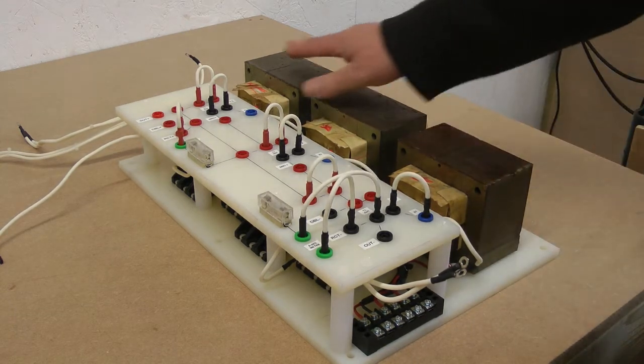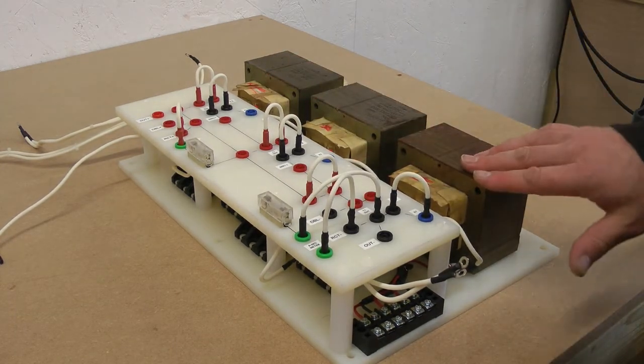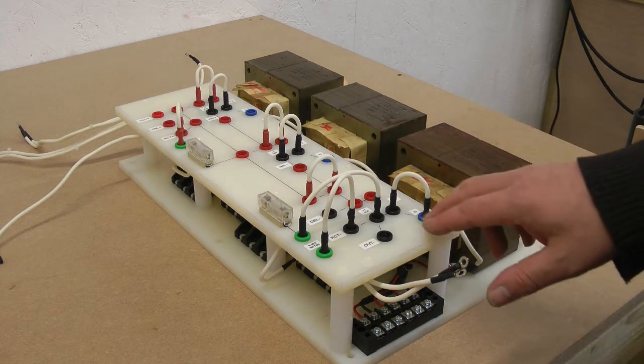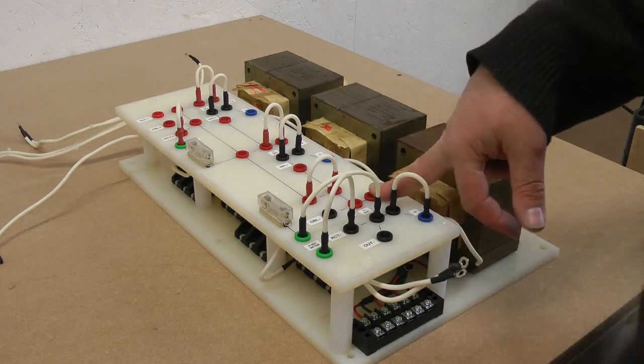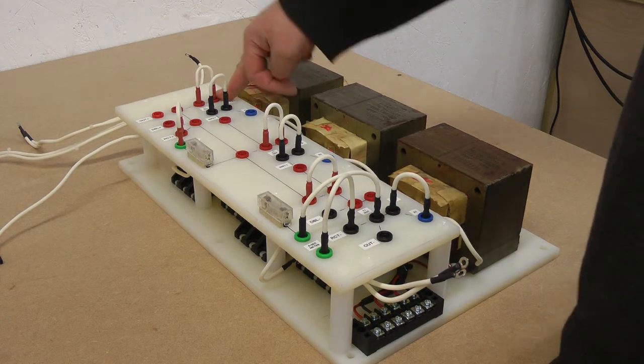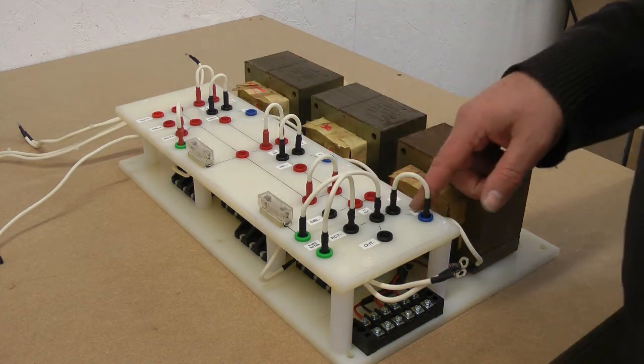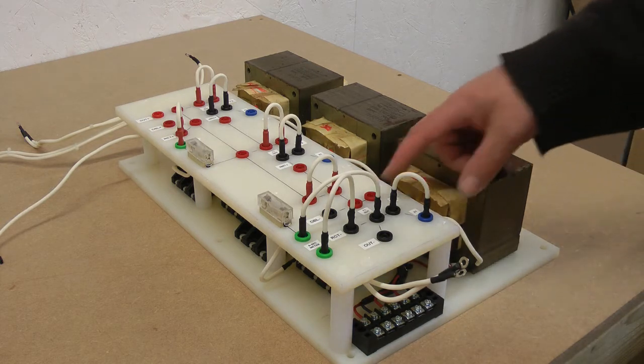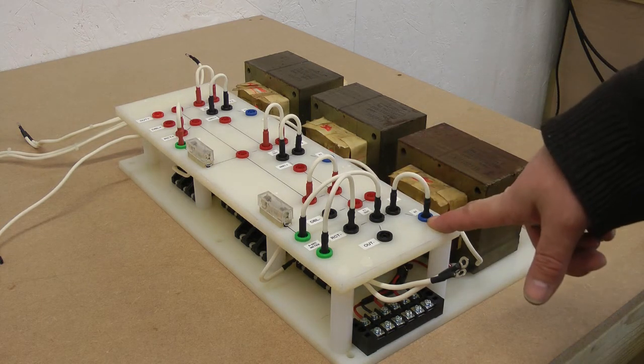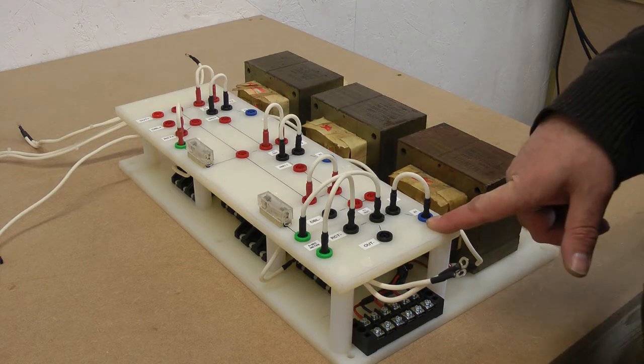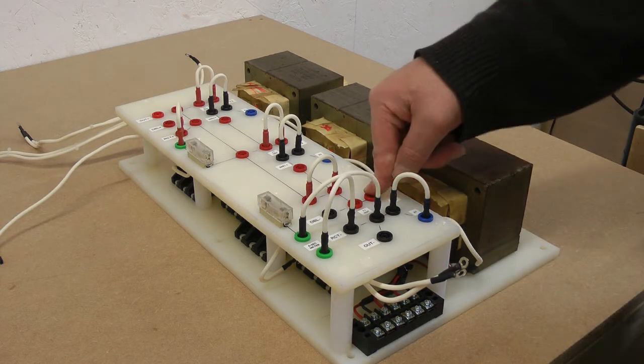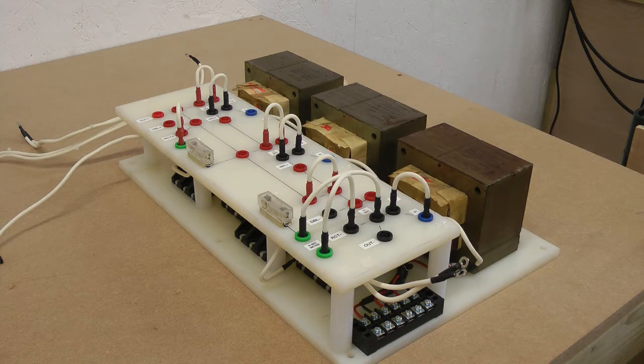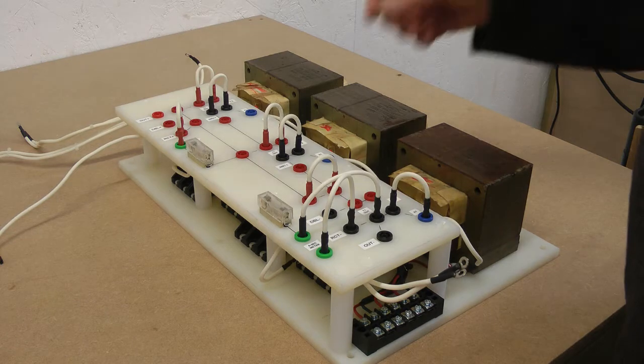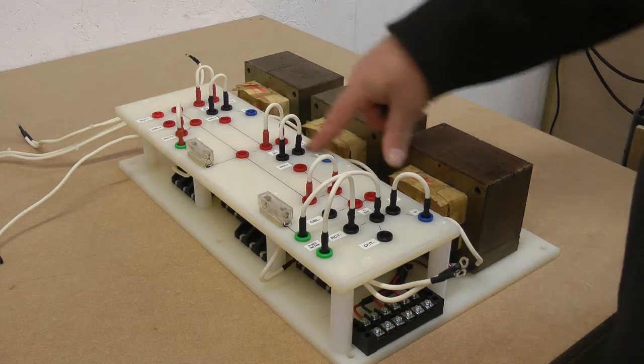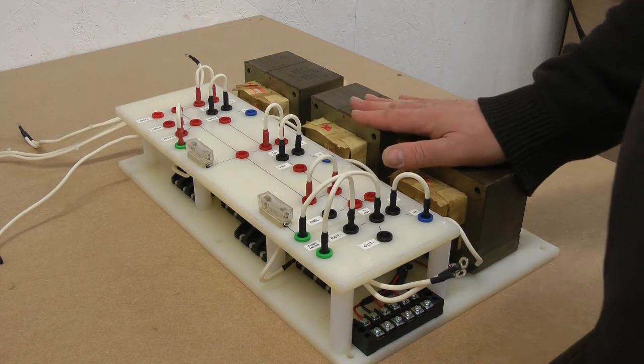For example, if you were running these 3 in series, where this end is at minus 3 kilovolts and this end is at plus 6 kilovolts, with all 3 in series, you're not going to be connecting the bottom end down to the transformer earth, because in effect you're running at minus 3 kilovolts for the bottom end. That is an example where you would not be connecting the transformer earth to the line supply earth.